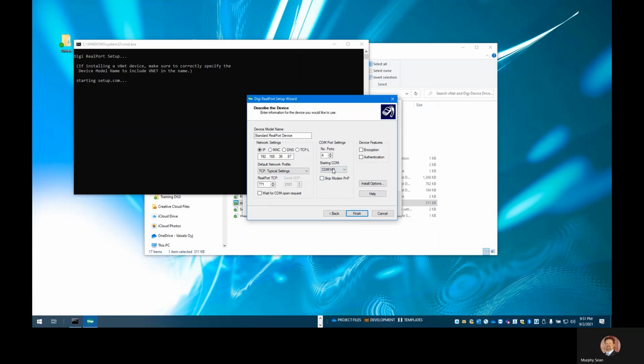Those are the numbers that you need to keep in the back of your head, because that COM port is the one that viewLinc is actually going to talk to. So when you go through the device discovery for the particular data logger that's connected to it, that is the COM port number that you would actually enter into it. There's an automatic discovery tool that's built into viewLinc, so typically you don't have to do that. But in this case, you need to know what the COM ports are for the device. It's good to document this down to know what COM ports you had mapped.